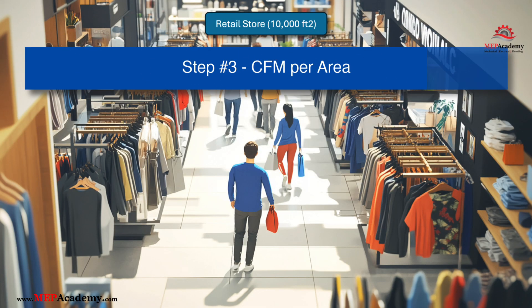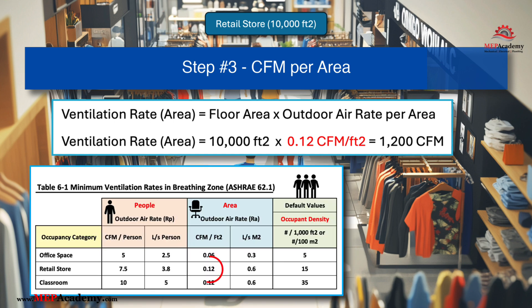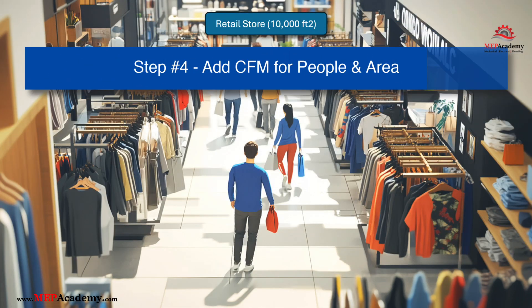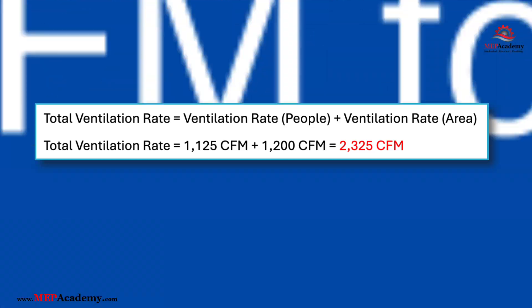Step 3: Ventilation rate (area) = 10,000 sq ft × 0.12 CFM per sq ft = 1,200 CFM. Step 4: Total ventilation rate = 1,125 CFM (people) + 1,200 CFM (area) = 2,325 CFM. Therefore, for this retail store, the required outdoor air ventilation rate is 2,325 CFM.